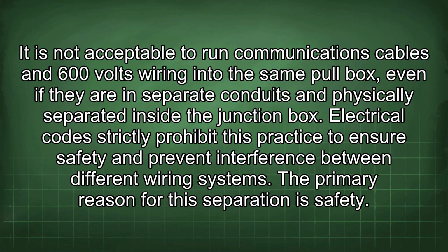It is not acceptable to run communications cables and 600 volts wiring into the same pull box, even if they are in separate conduits and physically separated inside the junction box. Electrical codes strictly prohibit this practice to ensure safety and prevent interference between different wiring systems. The primary reason for this separation is safety.